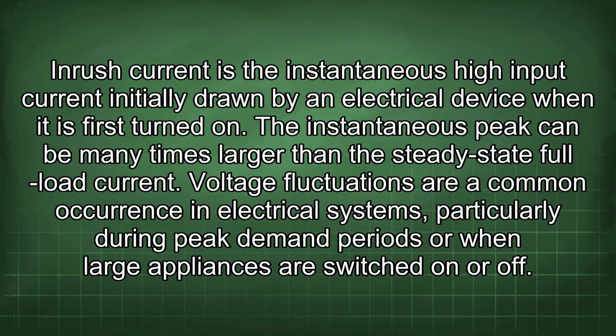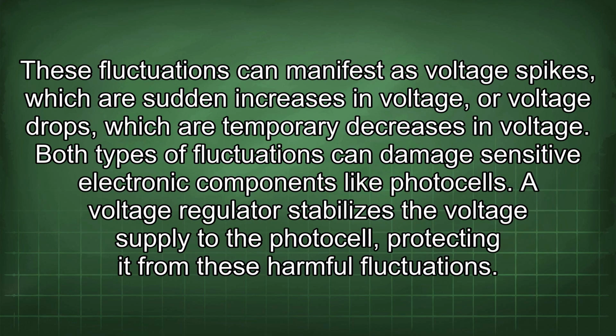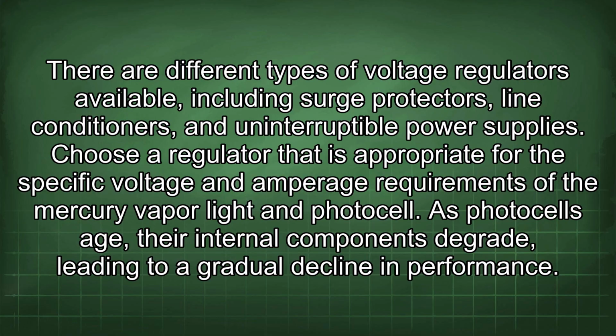Voltage fluctuations are a common occurrence in electrical systems, particularly during peak demand periods or when large appliances are switched on or off. These fluctuations can manifest as voltage spikes, which are sudden increases in voltage, or voltage drops, which are temporary decreases in voltage. Both types of fluctuations can damage sensitive electronic components like photocells. A voltage regulator stabilizes the voltage supply to the photocell, protecting it from these harmful fluctuations. There are different types of voltage regulators available, including surge protectors, line conditioners, and uninterruptible power supplies. Choose a regulator that is appropriate for the specific voltage and amperage requirements of the mercury vapor light and photocell.